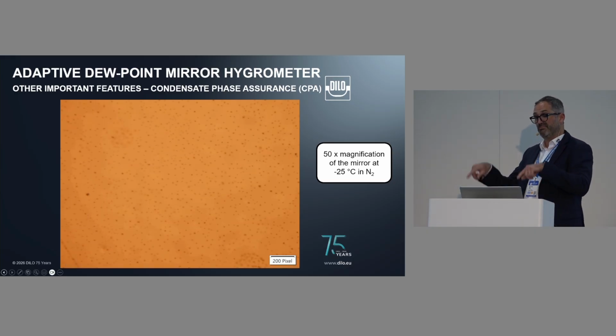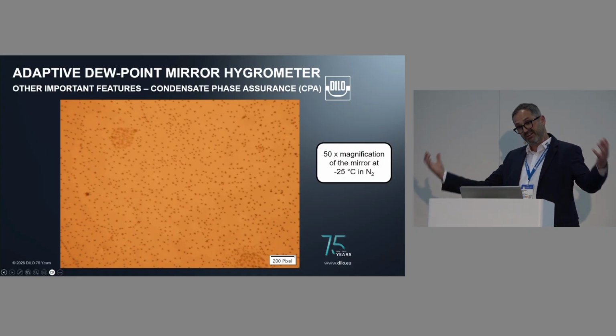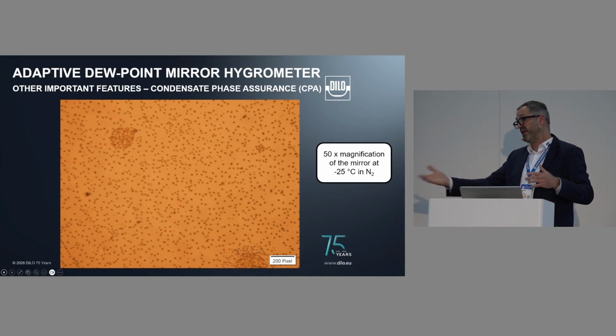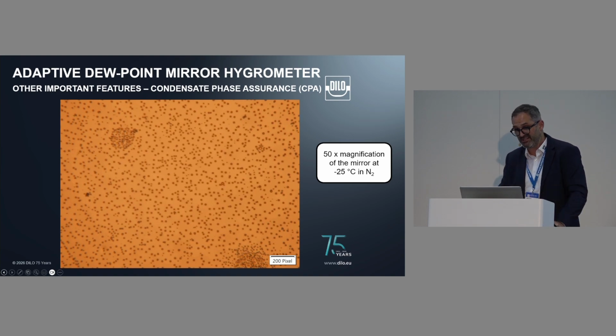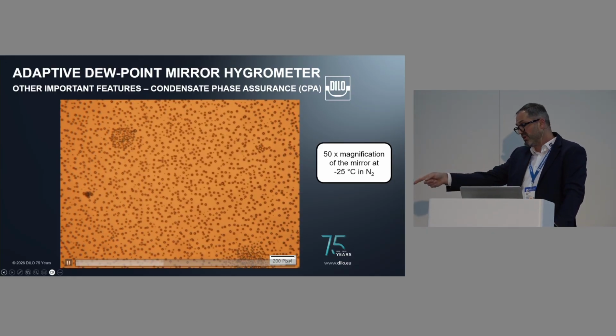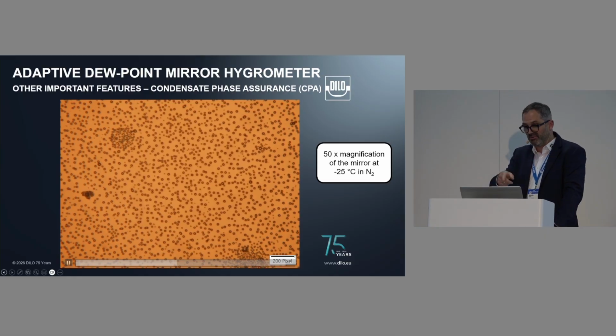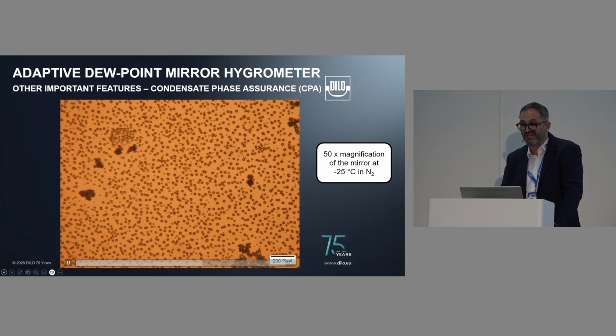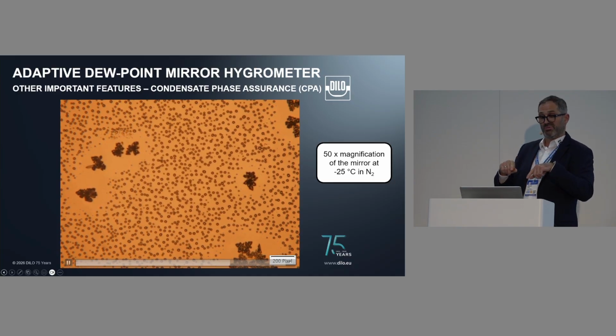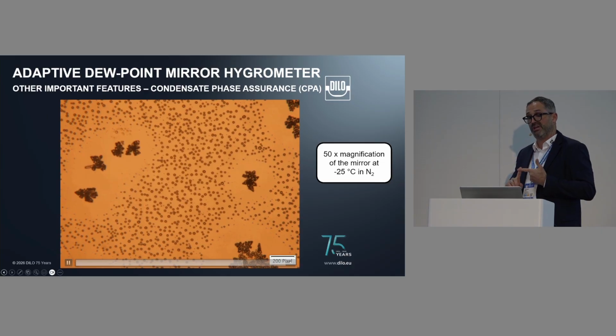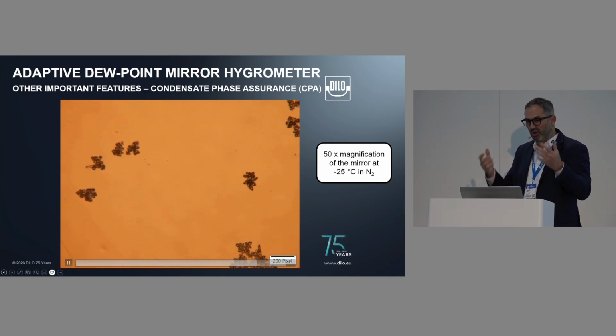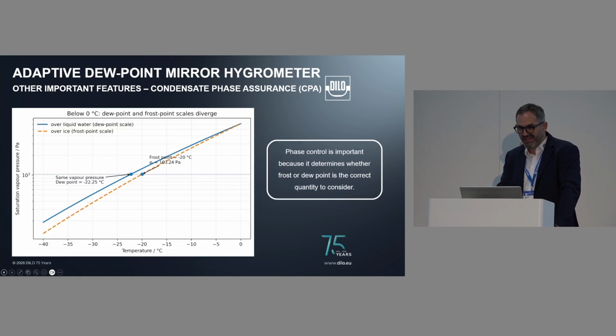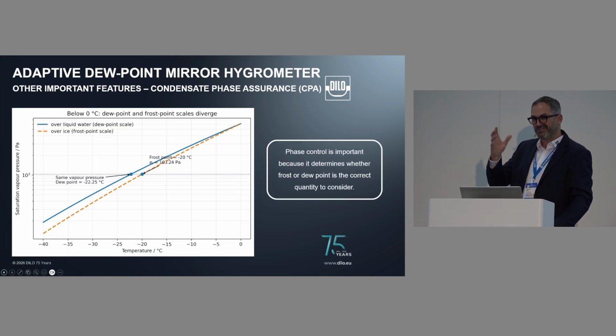So what you see here is a measurement at minus 25 degrees C, and at minus 25 degrees C you would expect, okay, on my mirror that's ice, but it's not the case. As you can see here, a lot of liquid droplets are forming, and if you would then say, okay, I have to take the frost point, you are wrong. This is clear evidence. So you have a lot of droplets at minus 25 degrees C, and then on some nucleation sites ice crystals are forming. And in this stage, neither the frost nor dew point is correct. So you have to make sure that you know the phase on your mirror. And it can make a difference of, let's say, 10%.